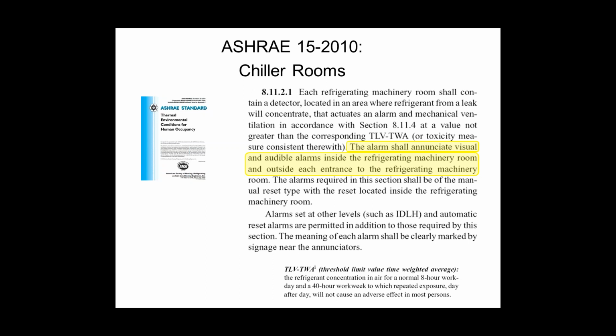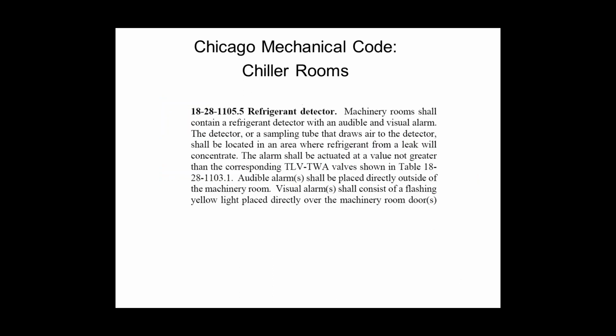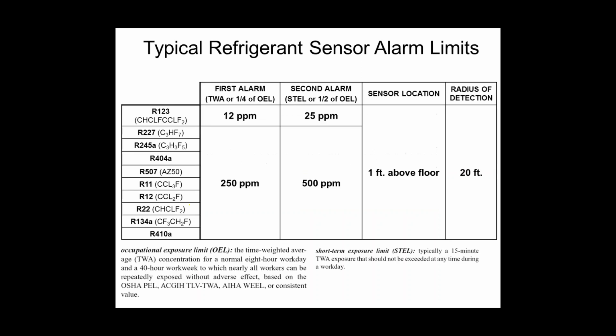You have to audibly and visually alarm inside the room and outside every single door to the room based on the TLV, TWA numbers, which typically means 8-hour work day or 40-hour work week level. If you are in the City of Chicago, the language is completely different in the code, but it basically says the same exact thing, which means you have to have an audible and visual alarm outside every single door to the room. So basically it ends up telling you to do the same thing as far as the controls are concerned. There's other stuff that's different, but controls-wise, have alarms inside the space and outside the doors to that space.